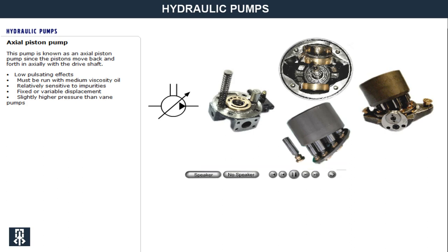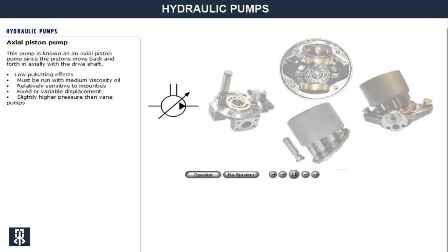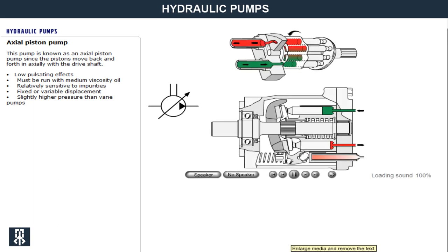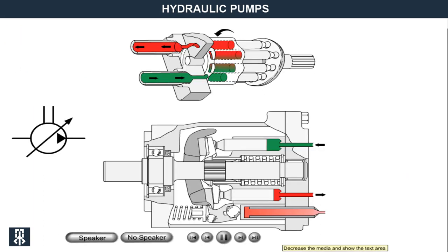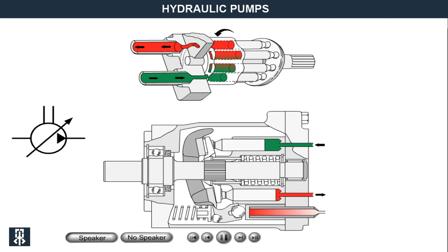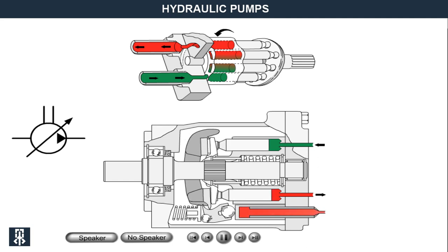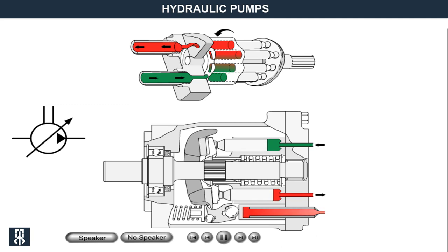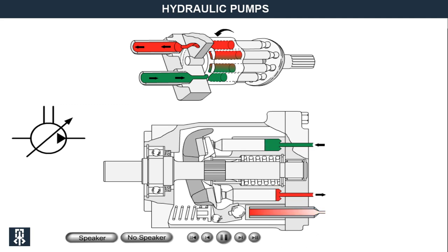This pump type is called an axial piston pump since the pistons move back and forth in parallel with the drive shaft. The pump is built up of a pump housing where a rotating shaft drives a cylinder drum with a number of cylinders and pistons. The pistons are connected with the drive shaft via a drive disc. The pumps are most often variable, meaning that the piston's stroke, and thus the pump's displacement, varies from minimum to maximum displacement.